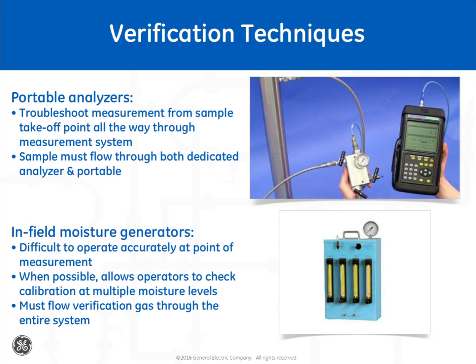Some have had success with dual dilution moisture generators, permeation tube moisture generators, and with calibration cylinders, when great care is taken to control the environmental factors that can impact their accuracy. By employing one-point offsets or multi-point offsets, one may use verification techniques to calibrate the sensor or to adjust its calibration in the field. These techniques are not as accurate as laboratory techniques, where moisture generation and data collection are properly controlled.